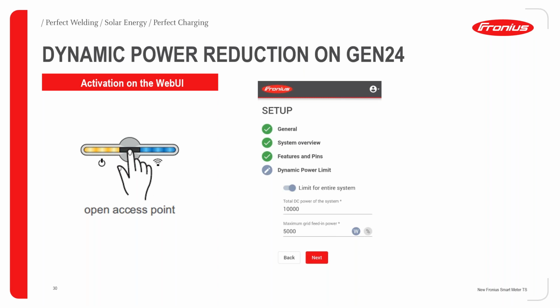So as soon as you activate the inverter with the button one touch, you can access the interface page. Then you can go directly to the setup menu. Under the setup menu, you will have the option called dynamic power limit. Then you can choose the total DC power of the system, and then the maximum allowed grid feed-in power. You can enter it in the same way, in watts or by percentage.